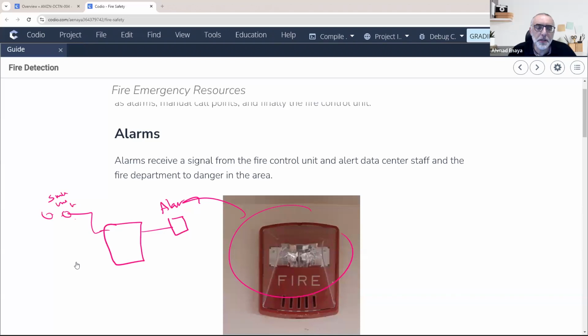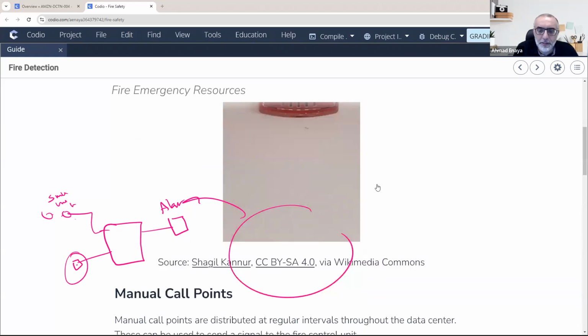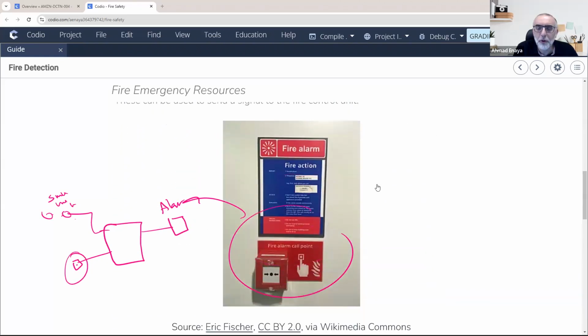In addition to this, there should be some manual option. Maybe you as a human can see the fire, but it is not detected yet by the system. Do you want to wait for the system to detect the fire? Or there should be a way for people to report the fire immediately and alarm everyone. Yeah, thank you, Joshua. So there should be a way to manually trigger the alarm. And that's why typically in the fire system, you'll find some manual call points.